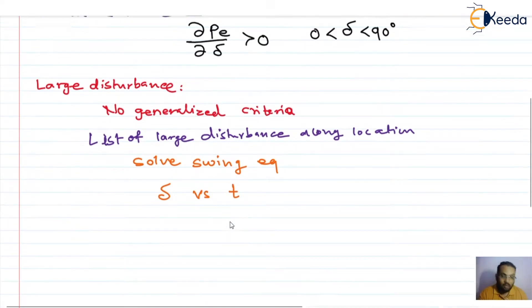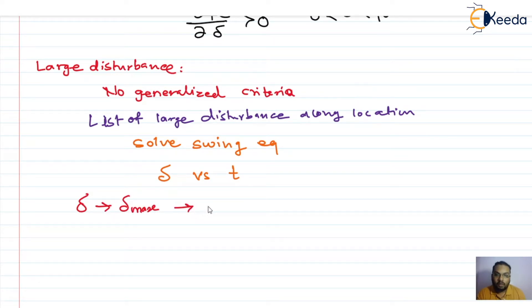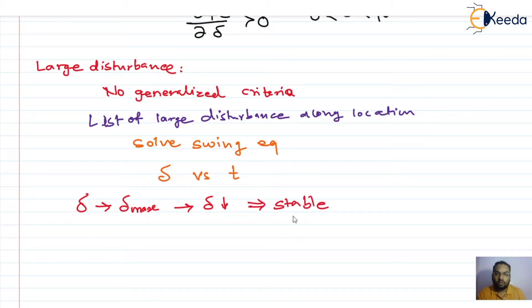From the swing curve, if the rotor angle delta, after attaining a maximum value, starts decreasing, then we can assume the system will be stable for large disturbances — that is, the system has transient stability. If, however, after attaining the maximum value the rotor angle does not decrease, and the rate of change of the rotor angle is continuously increasing, then the system will not be stable — it will not have transient stability.